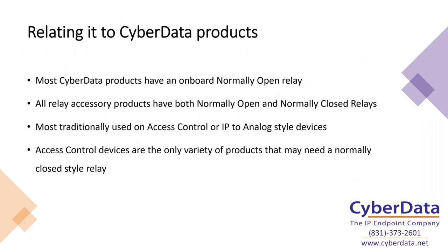When dealing with relays, it's typically either access control style setups — where you remotely unlock a door — or connecting to an analog amplifier. In the vast majority of connections for either of those areas, they're traditionally going to use a normally open style circuit where nothing is going on and then everything connects and it works. In the access control realm, that's what energizes the actual door strike that unlocks the door — normally it's not engaged so the door is locked, you close the relay, circuit is completed, door is unlocked, and somebody can pass through.